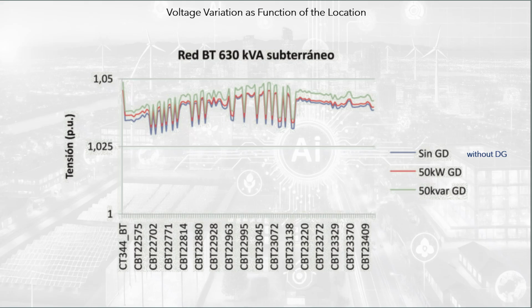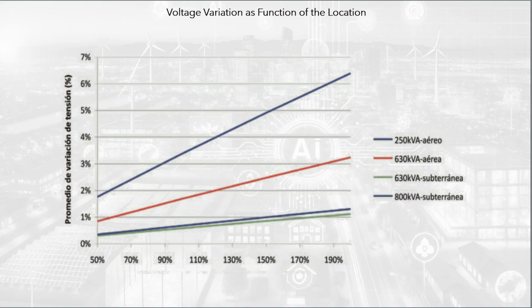In this network, the impact of distributed reactive power is greater than that of active power, since all the nodes are very close to the CT and the voltage drop in it is more important than that which appears in the lines. The figure shows how the voltage of the different low voltage networks varies if the level of DG penetration increases, from 50% to twice the power of the net demand. The injection is homogeneous in all the nodes of the network.